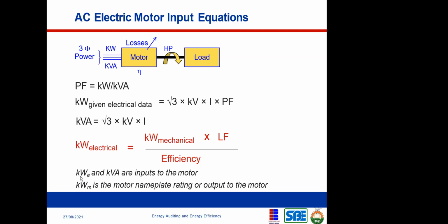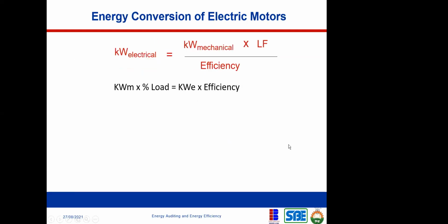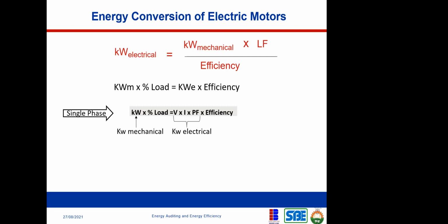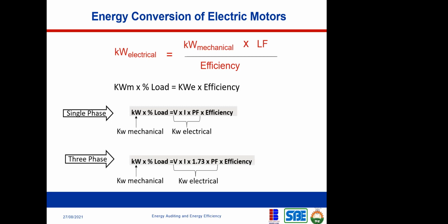Kilowatt electrical is the input to the motor, while kilowatt mechanical is the motor nameplate rating, or output. Now let us make kilowatt mechanical the subject of the formula. This is just normal formula manipulation. So kilowatt mechanical times the load factor, the percentage load, is equal to kilowatt electrical times efficiency, more like cross multiplication. So this is what you have.